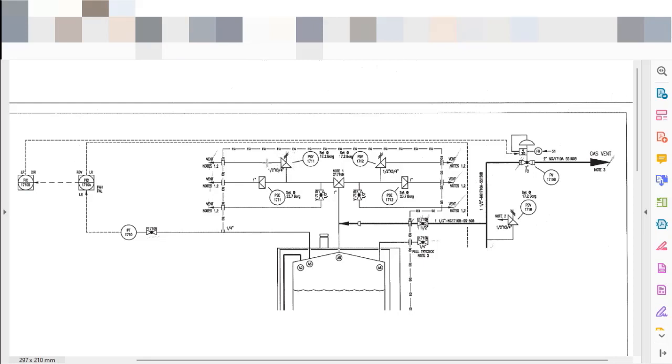See that this type of relief device is the direct actuated valve, because the pressure of the fluid is responsible for opening the orifice of the safety valve. If for any reason my pressure keeps increasing, I can reach the set point of the rupture disc, and the rupture disc will be responsible for releasing the pressure of the vessel.